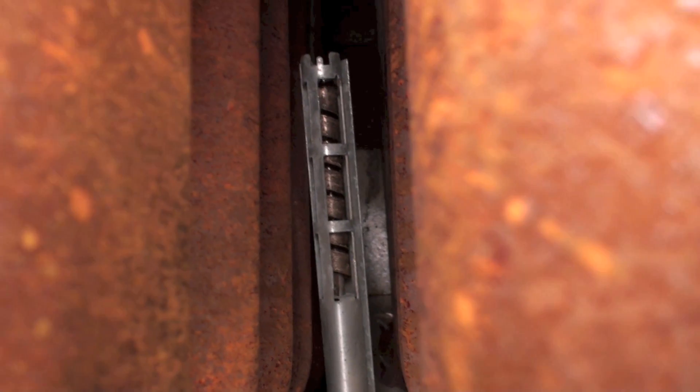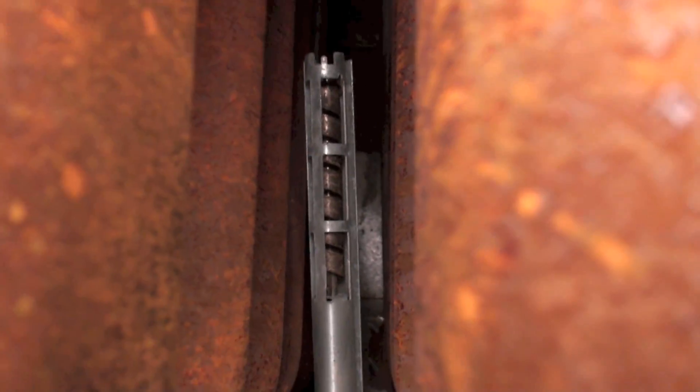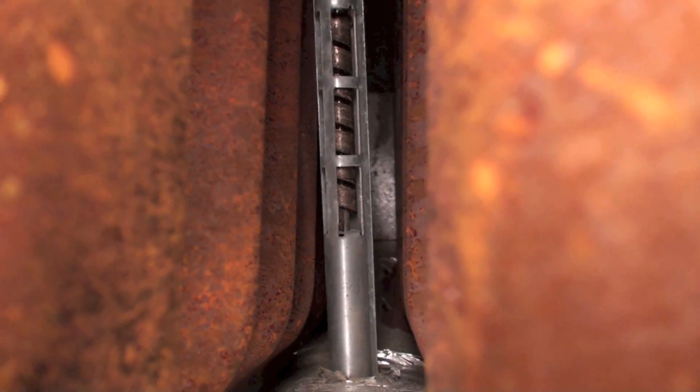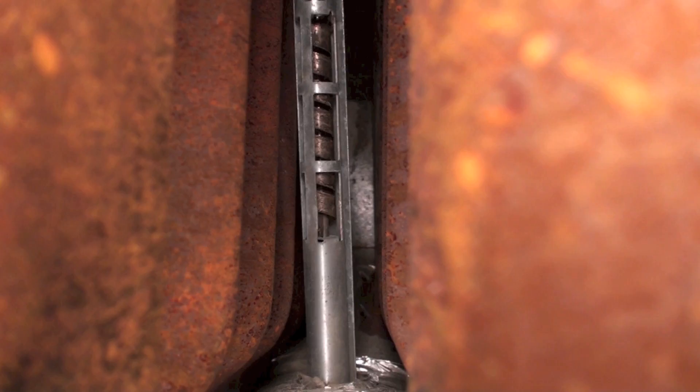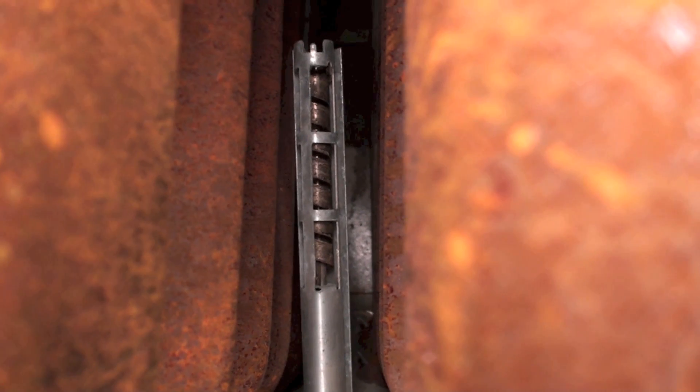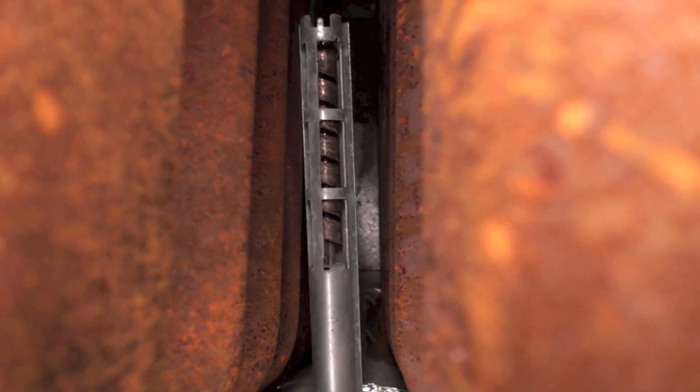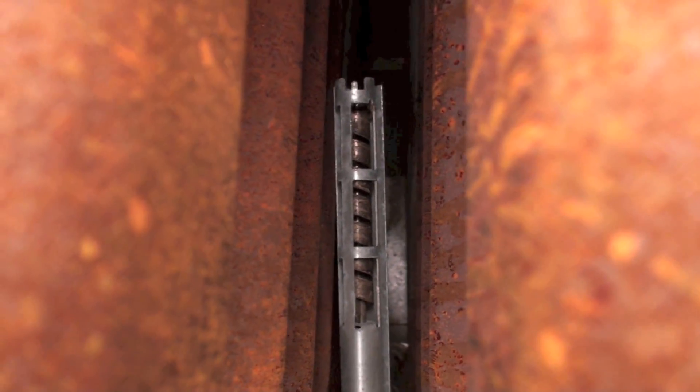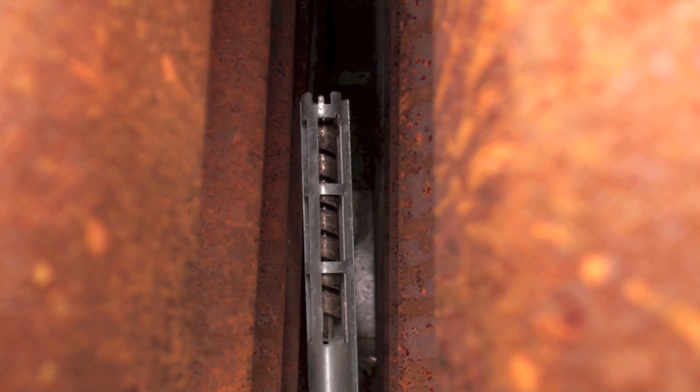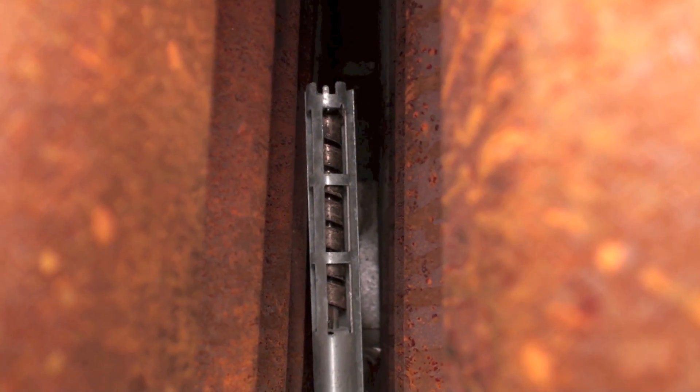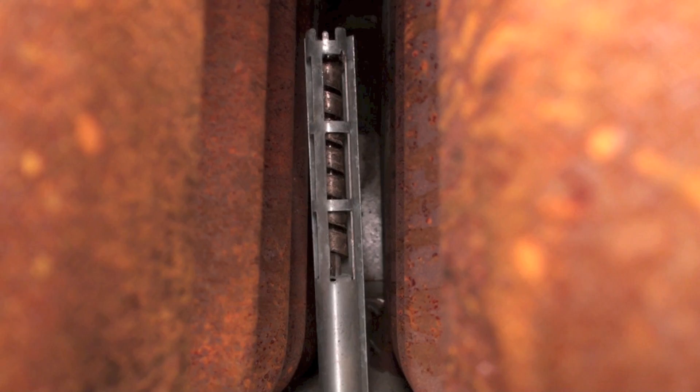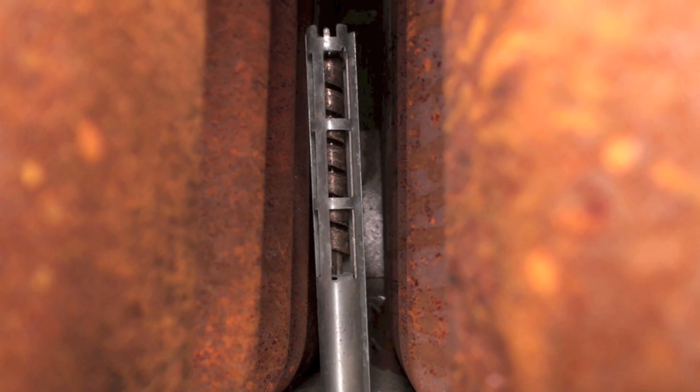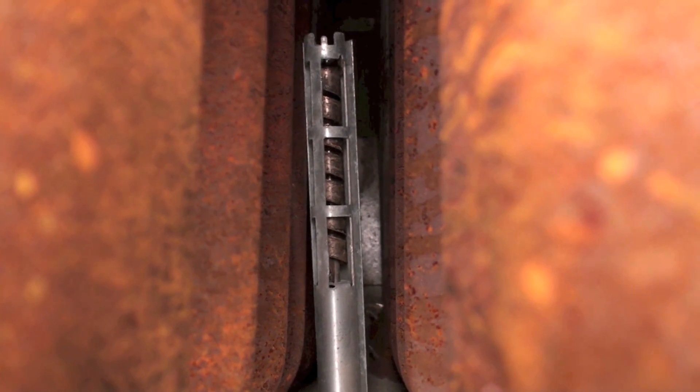I can see it penetrates in there—that shield is on the bottom. And when that heat exchanger starts to warm, what happens is both convective heat and radiant heat come off of that heat exchanger and make the switch make.